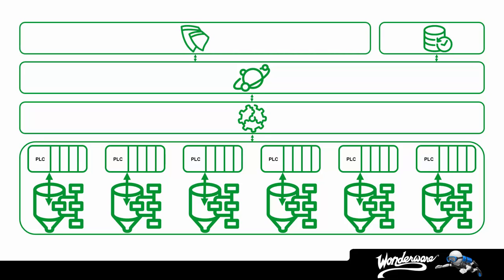So, do we only need four licenses? Well, that depends. For example, do we really want to rely on a single computer running with our device access license to handle the communications to all six processes and all the controllers related to it? While it's possible for the software to do that, it's probably going to be better if we wouldn't. It would probably be best if we distributed the communications across multiple computers. This helps ensure availability if one of the computers isn't working, like when Microsoft updates are being installed or heaven forbid the hard drive fails or something like that.